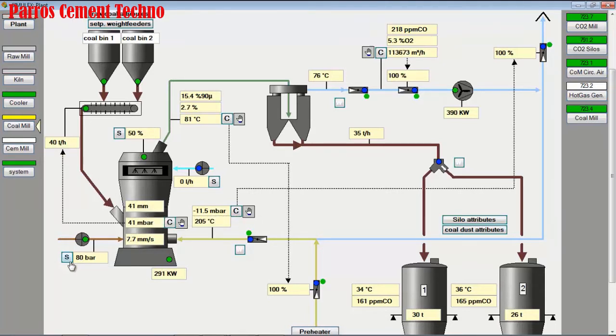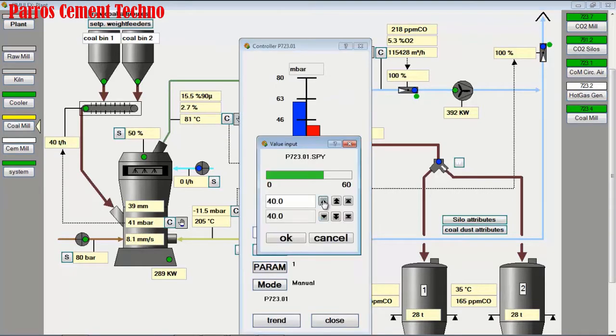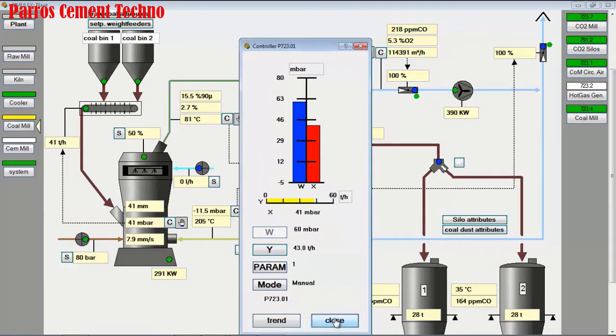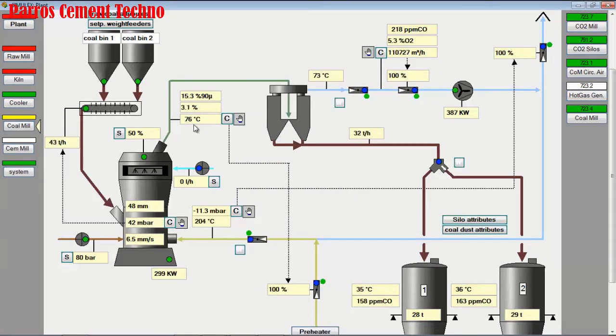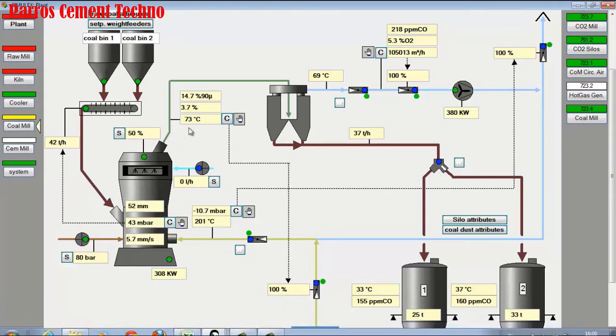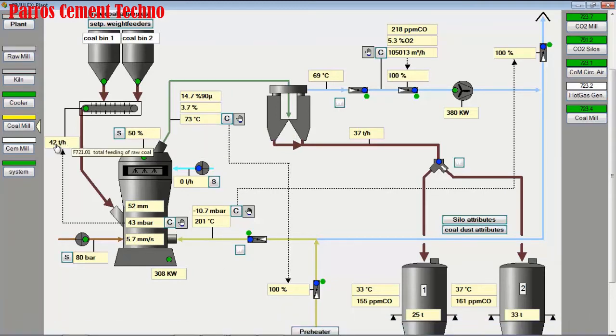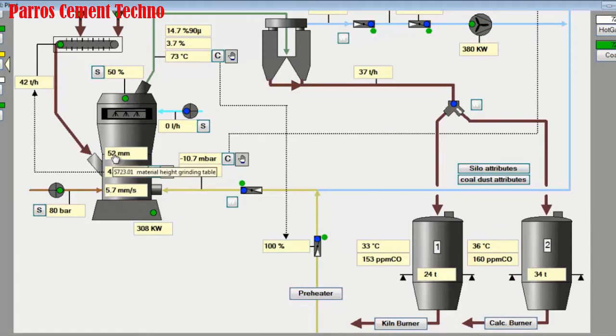The mill outlet temperature is still high — try to keep it below 75 degrees Celsius or around 70 degrees Celsius. The vibration is still above 7, the mill feed is 40 tons per hour. We increase the mill feed by about 2 tons per hour so that the mill outlet temperature decreases and the vibration also decreases. The mill outlet temperature drops and the mill vibration also drops.